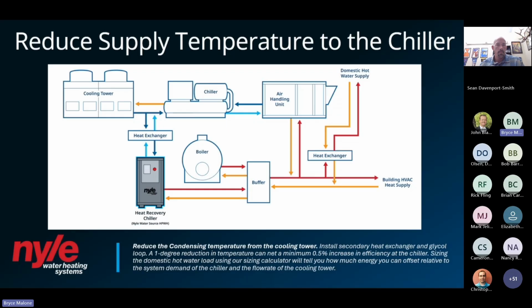One of the benefits on the domestic side is its ability to be deployed in a cooling tower chiller application. In this case, because of how heat pumps work, a heat pump water heater is actually going to be operated in a heat recovery chiller application where we're going to be sucking all this energy from all this existing HVAC equipment, and then I'm going to lower your condensing water temperature. By doing that, you're going to pick up not only higher COPs on your domestic hot water performance, but now you're actually going to impact the system's overall COP and overall system efficiencies. So for every 1 degree of colder water I'm able to run back to your cooling tower, your chiller, you're going to pick up anywhere between 1.5% and 2% of increased efficiencies.